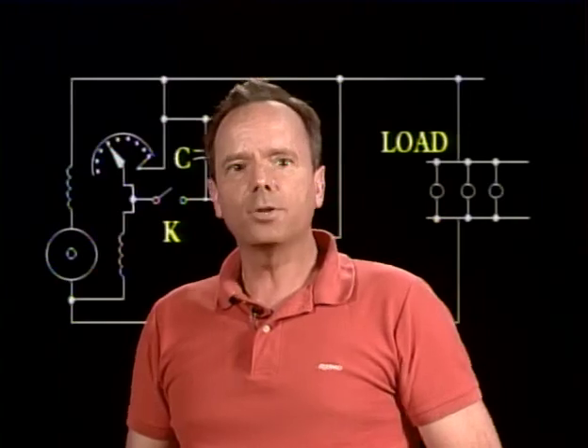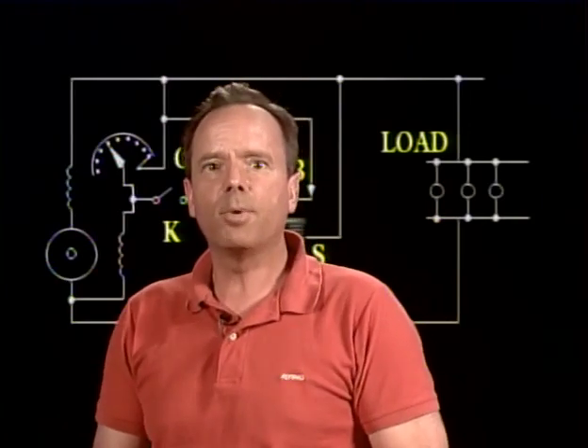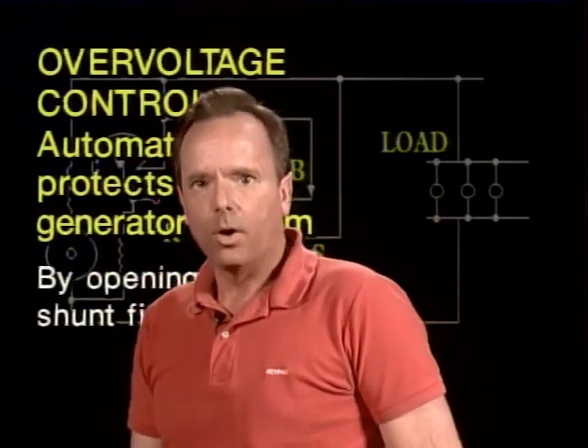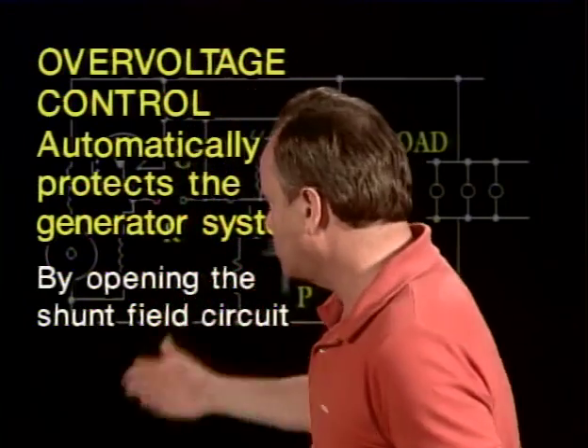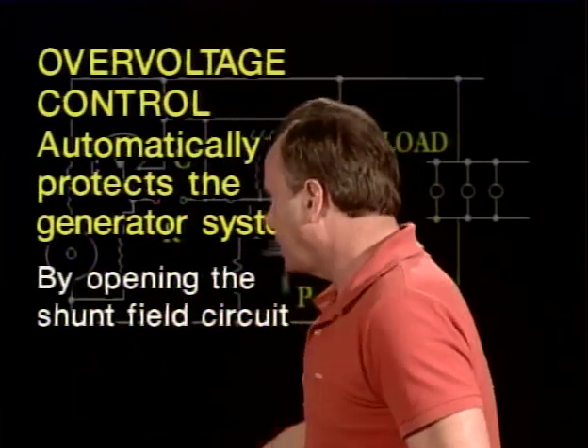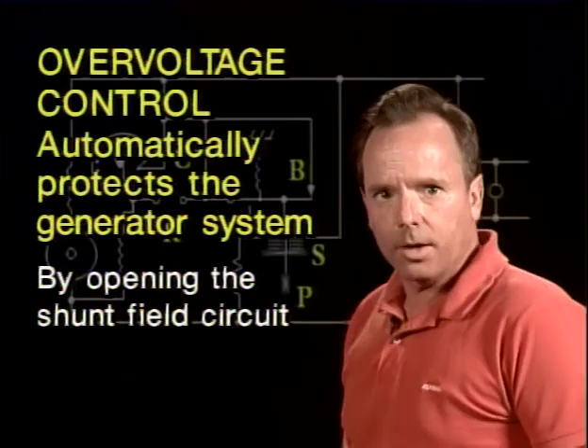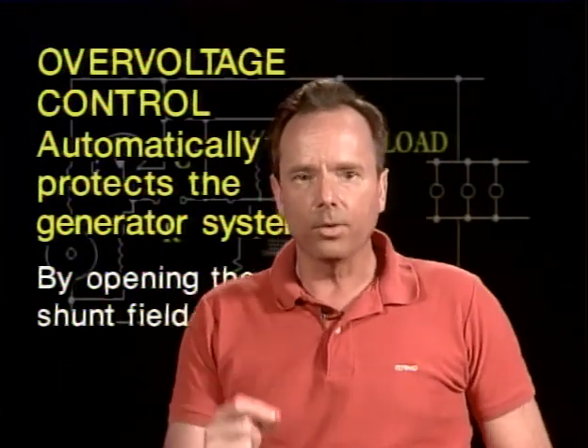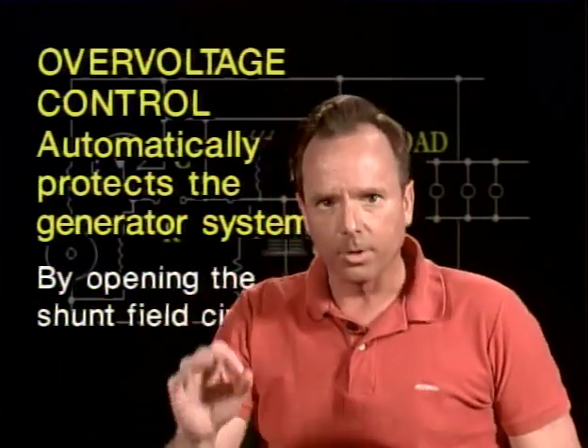So what happens if the reverse current cutout relay contact fails to open? Then what's going to happen is you're going to motorize the generator. All right, here's another thing they're going to ask you. They're going to ask you about the over voltage control on a generator. It automatically protects the generator system, and the way it does it is by opening the shunt field circuit. Once again, you're opening the field, and therefore you're controlling the voltage of the generator.